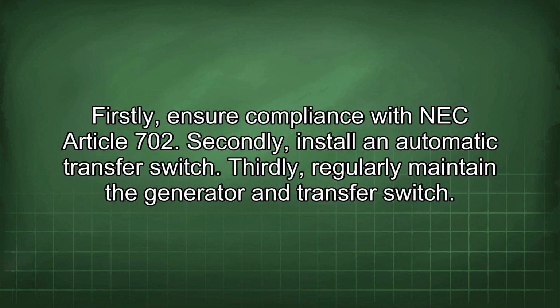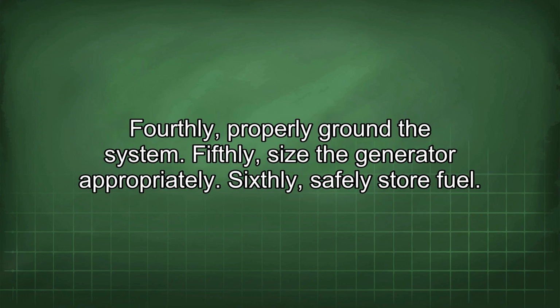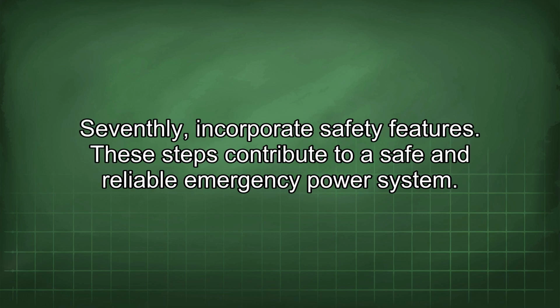Firstly, ensure compliance with NEC Article 702. Secondly, install an automatic transfer switch. Thirdly, regularly maintain the generator and transfer switch. Fourthly, properly ground the system. Fifthly, size the generator appropriately. Sixthly, safely store fuel. Seventhly, incorporate safety features. These steps contribute to a safe and reliable emergency power system.